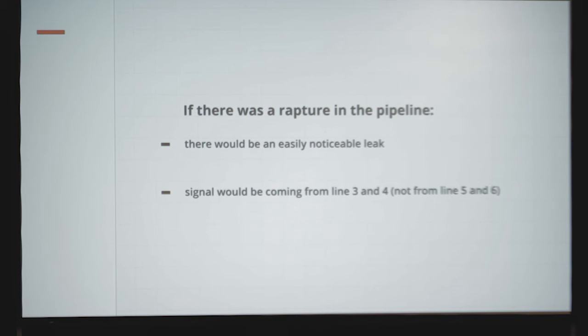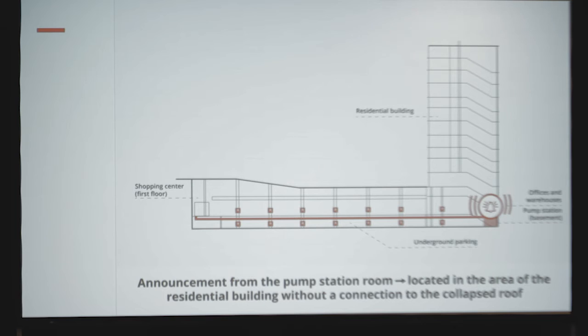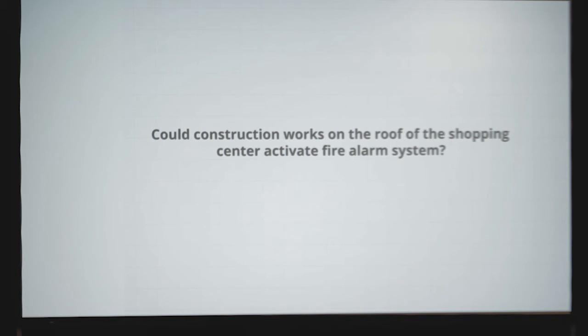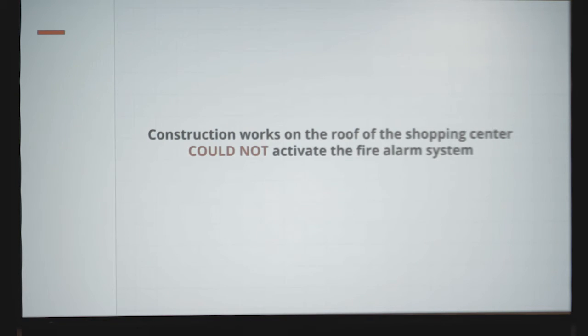So again, if there were a leakage, you would have seen it. If there had been a leakage on lines 3 and 4, we would have got the signal from lines 3 and 4, but not from line 6. So that's not possible. There was no intercorrelation. Could construction work do anything to the shopping center? Could it activate the fire alarm? It could not.